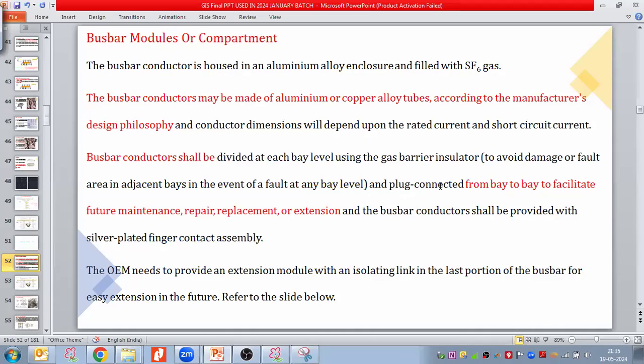And plug connected from bay to bay. The conductor is plug connected from bay to bay to facilitate future maintenance, repair, replacement or extension of the bus bar easily. And the bus bar conductor shall be provided with silver plated finger contact assembly as well. The OEM needs to provide an extension module, or the stop module or end module. When we are doing the extension in the future, then the extension module with an isolating link in the last portion of the bus bar is needed for easy extension in the future.